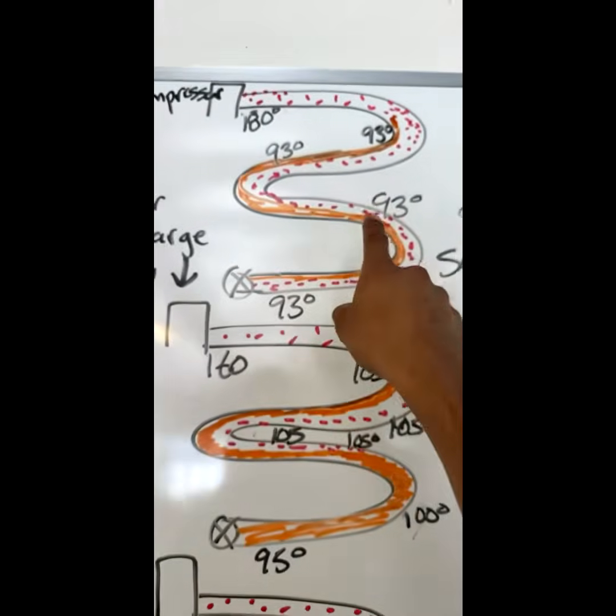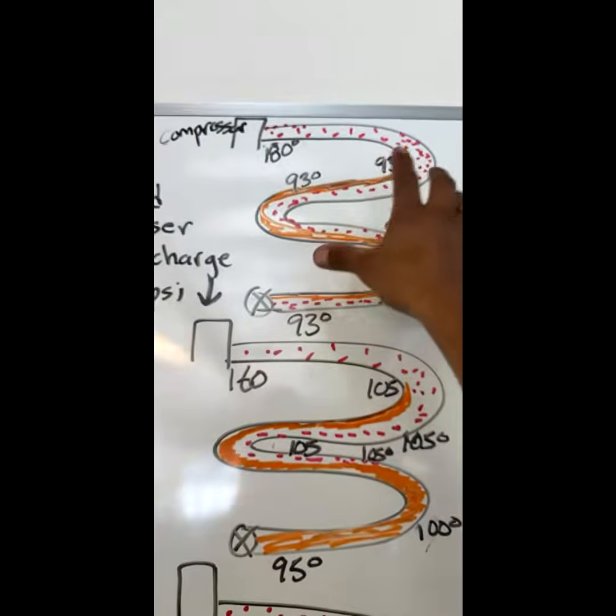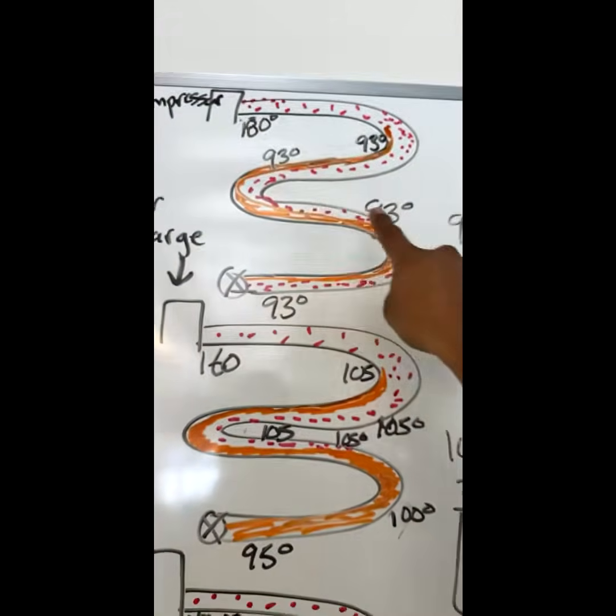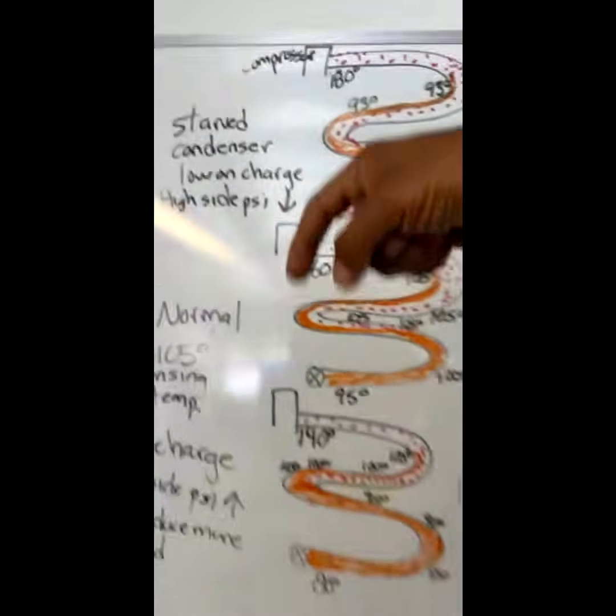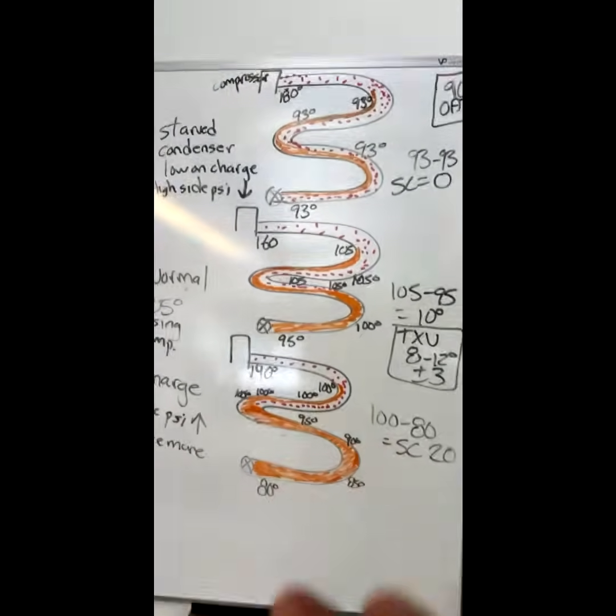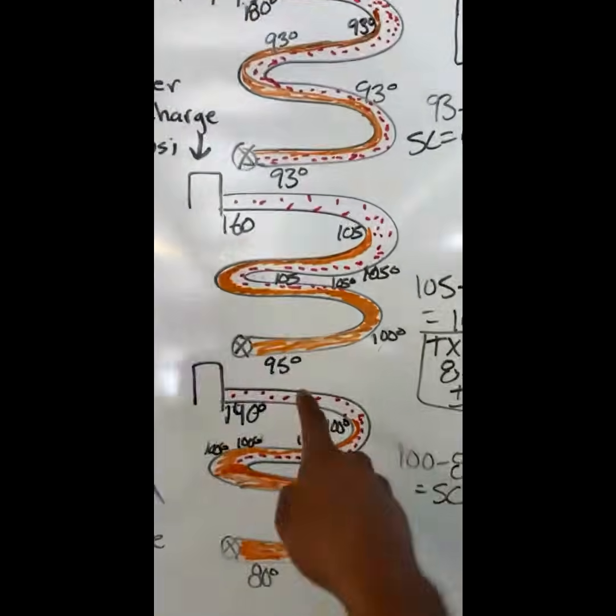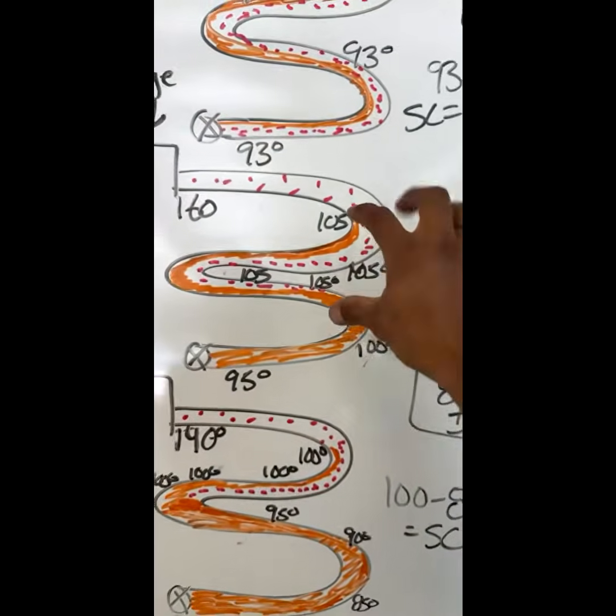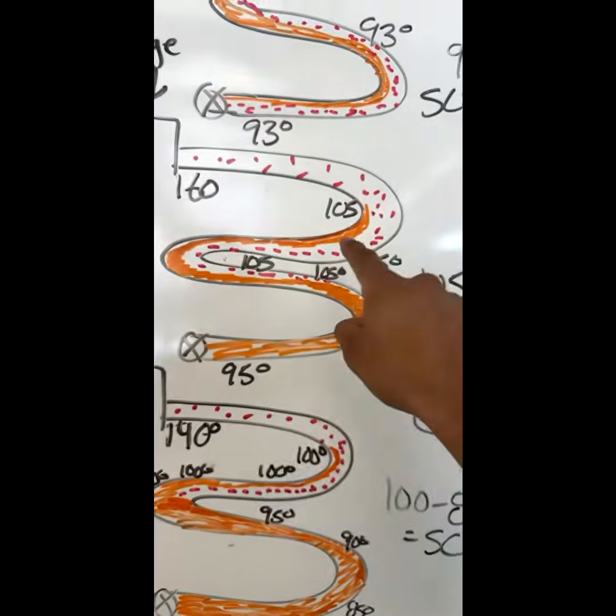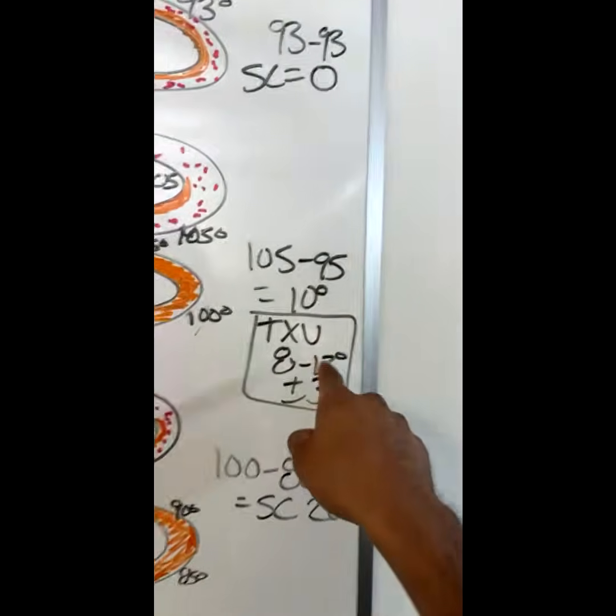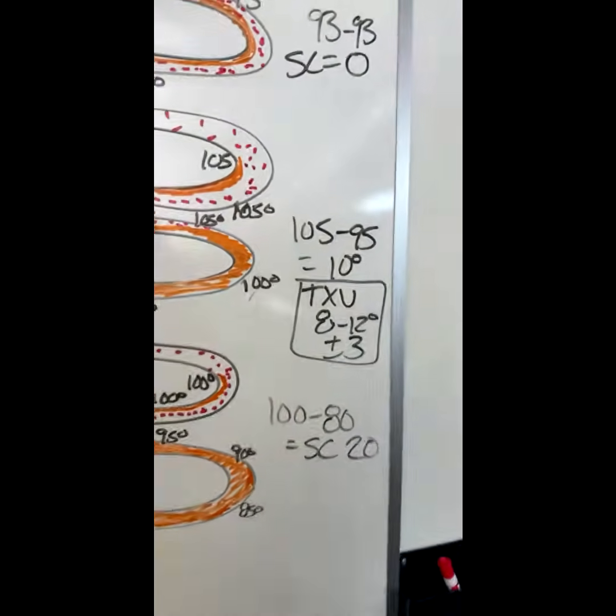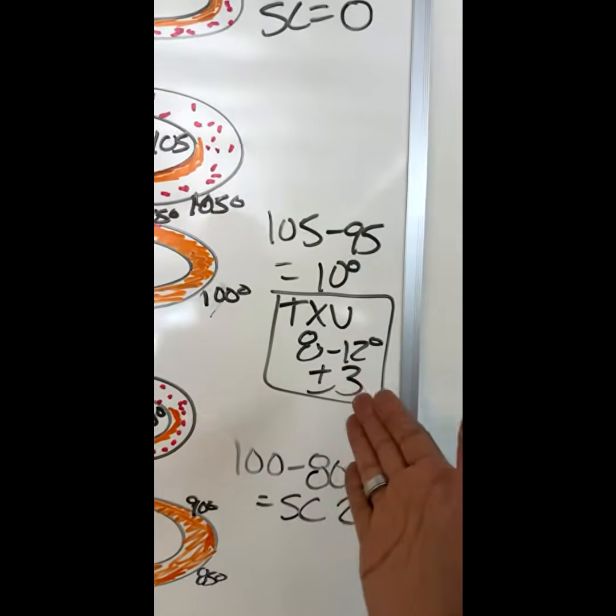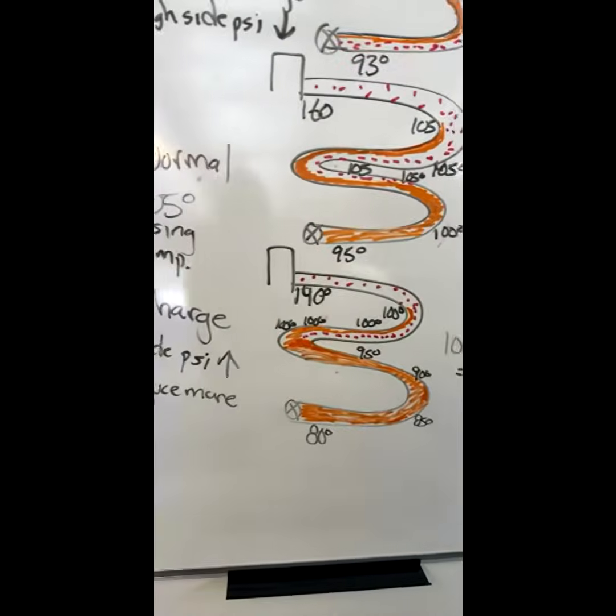because you don't have a big difference in heat. Most of your heat removal goes to removing latent heat, but it never produces liquid because you're low on charge, less volume. So with this one, just an example where it's saturated, 105 minus 95, subcool of 10. TXVs are 8 to 12 plus or minus 3, unless the manufacturer says otherwise on a plate.